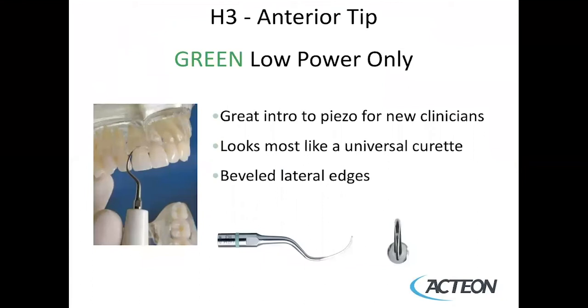The H3 tip is used on green, low power — you'll note that it has a green ring. The color-coded rings on the NewTron system tell you the maximum power setting. The H3 is an excellent tip for clinicians new to piezo, as it looks the most like a universal curette. We can transfer our skills from using a universal curette like a Columbia 13-14, Barnhart 5-6, or 4R4L, using the lateral surfaces and not the back. It has beveled lateral edges, making it excellent for calculus removal.